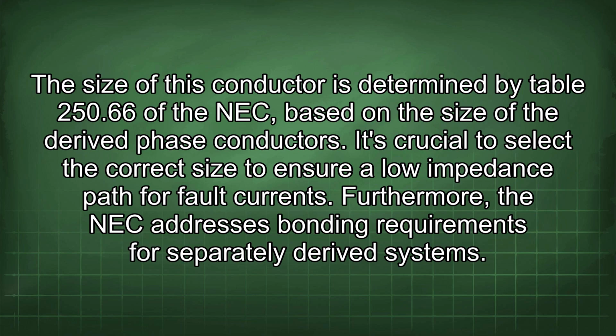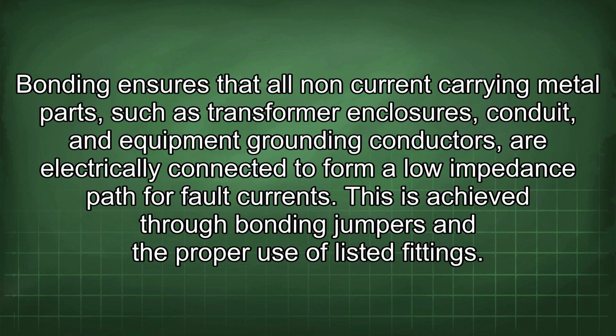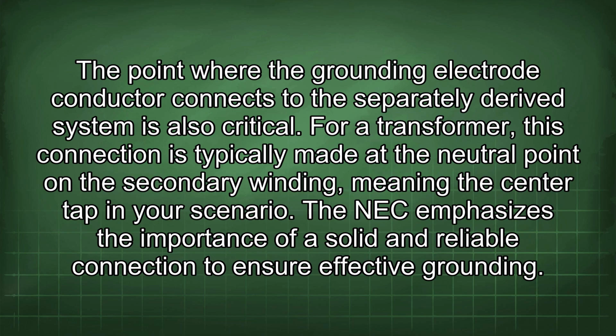Furthermore, the NEC addresses bonding requirements for separately derived systems. Bonding ensures that all non-current carrying metal parts, such as transformer enclosures, conduit, and equipment grounding conductors, are electrically connected to form a low impedance path for fault current. This is achieved through bonding jumpers and the proper use of listed fittings. The point where the grounding electrode conductor connects to the separately derived system is also critical. For a transformer, this connection is typically made at the neutral point on the secondary winding, meaning the center tap in your scenario. The NEC emphasizes the importance of a solid and reliable connection to ensure effective grounding.